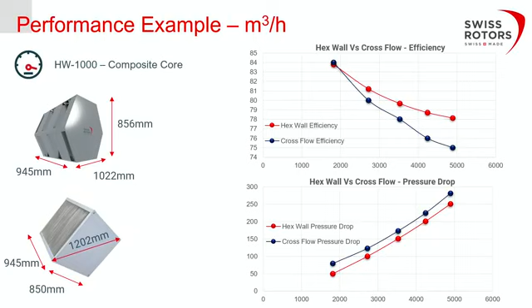If we look a little bit further up the range, when we start to get towards a higher level of airflow, it starts to come into its own at this point. So you can see that we have a higher level of efficiency, and we're also maintaining a slightly lower pressure drop on this unit. But one of the big advantages that you start to get when we get above HW1000 is that we really start to get a strong hold on making our physical air handling unit sizes smaller. So on the HexWall versus a Crossflow, we would be 346 millimeters less high and a little bit smaller in depth by 180 millimeters, with a higher efficiency and a lower cost.